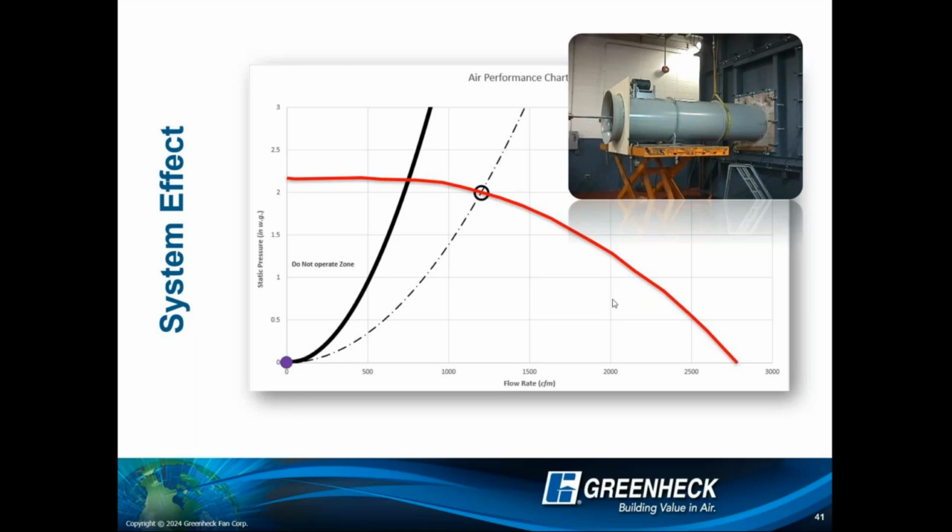Also, I don't know if you mentioned this or not, but right now in California, you actually cannot buy a fan with an FEI below 1.0. That's a California law, and as we all know in Massachusetts, we're not far behind them. So it will start to matter.